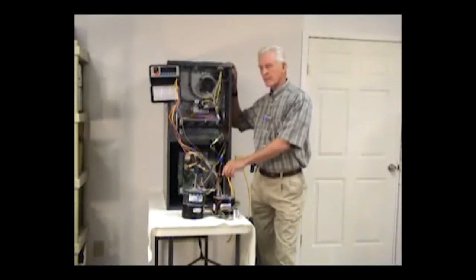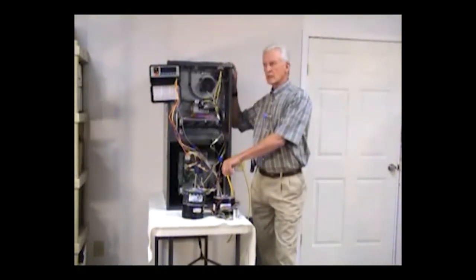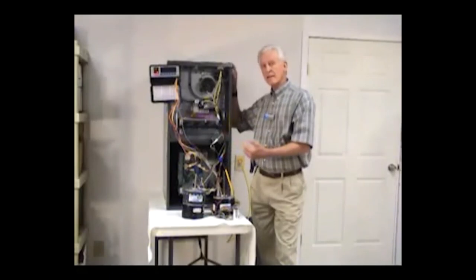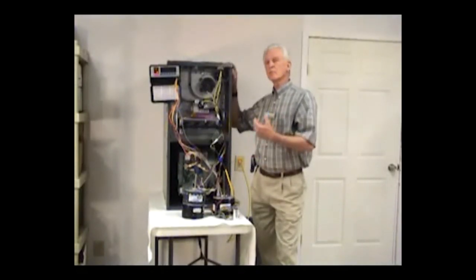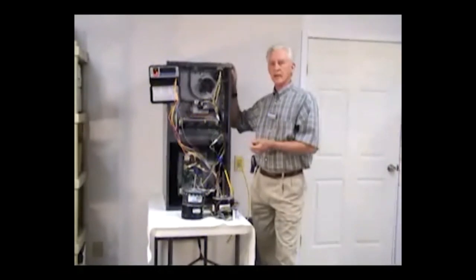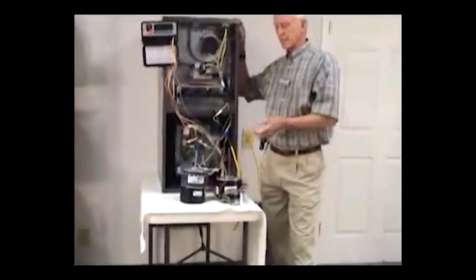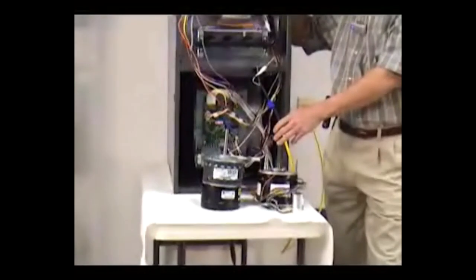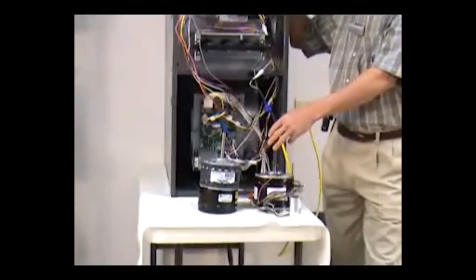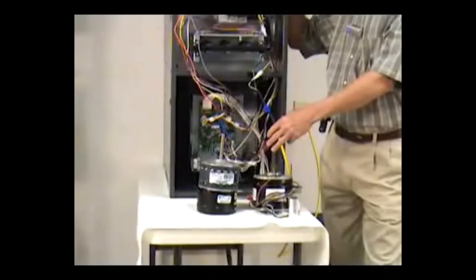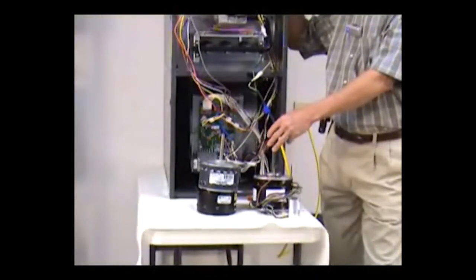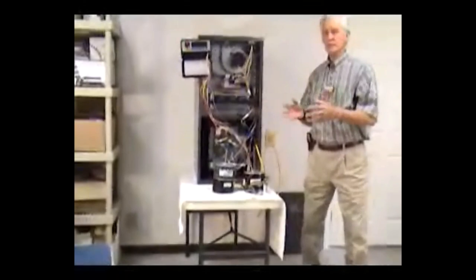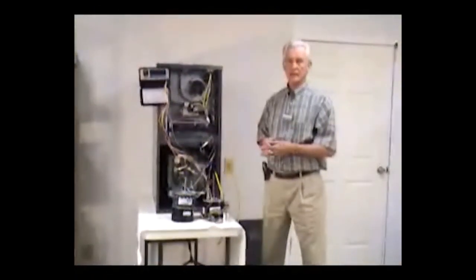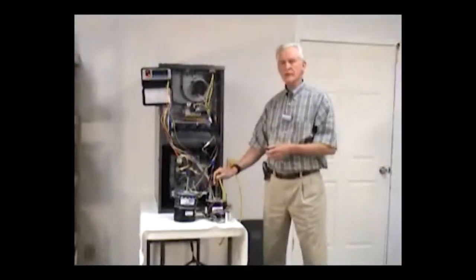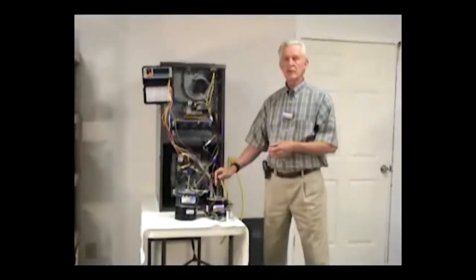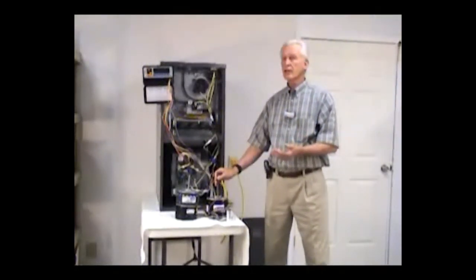The 1200 CFM of air is usually also going to come out in a specification sheet by the manufacturer that says that we will move typically 1200 CFM of air for the 3-ton application with this third horsepower motor. All right, we've got a duct system on it, return possibly, filters, coils, all of those things are going to create a certain amount of resistance, which for these purposes we'll call that external static pressure.